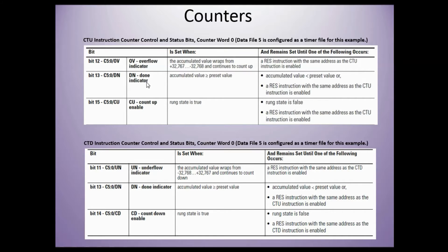The done indicator is when the accumulated value is equal to or greater than the preset value. The only way to have that bit low is if the accumulated value is less than the preset value or a reset instruction is used to reset that counter.